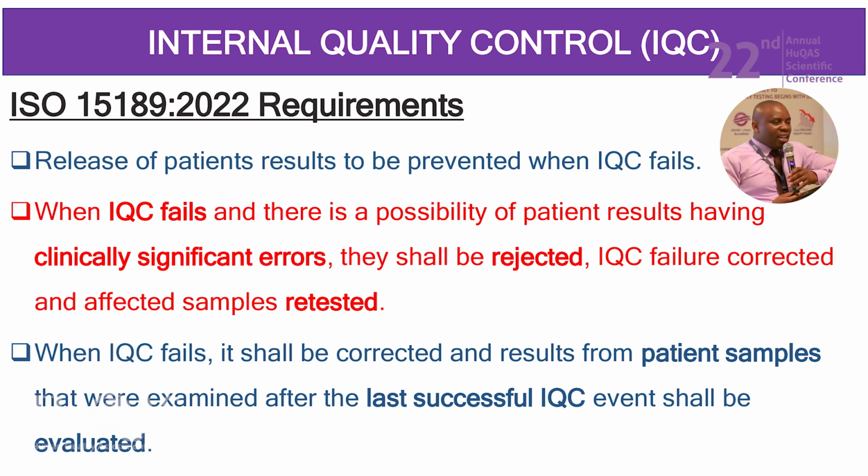We are used to running IQC every day. When you go to any facility in the morning, they have run an IQC. But then, when you interrogate the reports further, you realize out of the 40 tests they are doing, maybe 5 tests had a failure in IQC. But they are continuing releasing patient results in the course of the day without doing anything about the IQC failure.